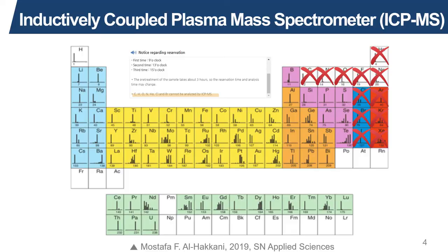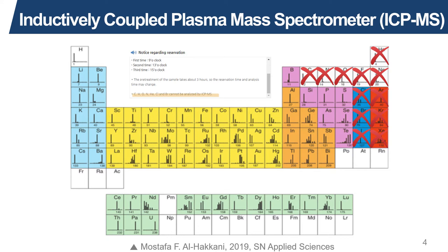Upon inquiry, the operators explained that this is mainly due to: one, the ionization energies of light elements which are considerably higher than that of the argon plasma; and two, the ionization efficiencies of certain elements due to matrix effects, a topic we will get into later. So remember, if you are interested in analyzing samples containing these elements, it is recommended that you look for other analytical techniques. You have been warned.